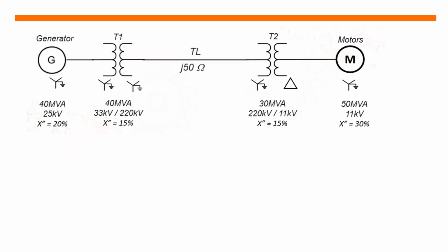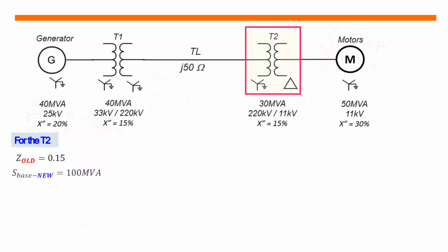For transformer 2, the old impedance is equal to 0.15. The new base power is equal to 100 MVA. The old base power is 30 MVA. The old base voltage is 11 kV. That is the old base voltage. The new base voltage for transformer 2 is still unknown.